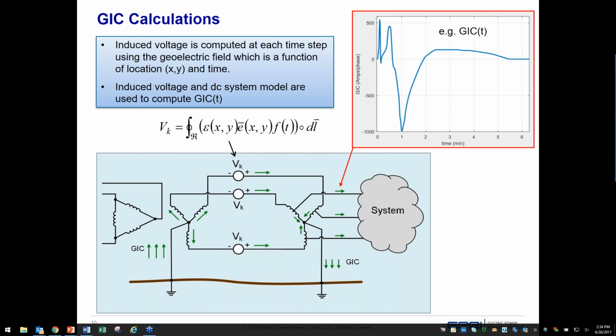If you have an electric stove and you turn the oven on, it doesn't instantly reach 350 degrees. It takes a little time to heat itself up to 350 degrees. And the same thing is true of a transformer. A transformer is very, very large, a tremendous amount of metal and a whole lot of oil. And even though you have very high levels of GIC current flowing inside the transformer for a period of time, with a nuclear blast E3, for several seconds, 60 seconds to even longer, you still have a gradual heating of the transformer. It doesn't instantaneously reach its potential temperature.